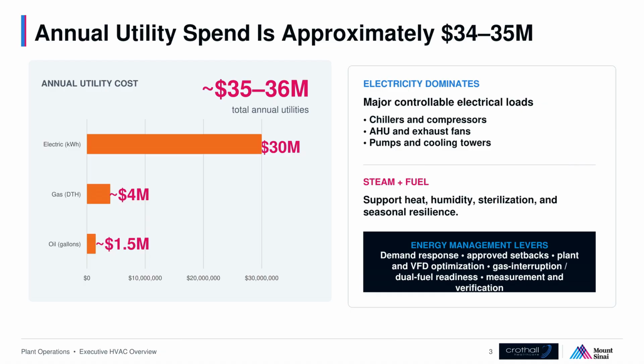On the steam side, interruptible natural gas service requires dual fuel readiness. When the utility calls an interruption, the boilers transfer off natural gas and onto fuel oil before the interruption begins, then stay on alternate fuel until it ends.